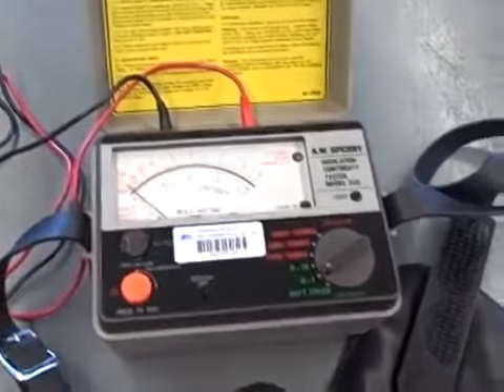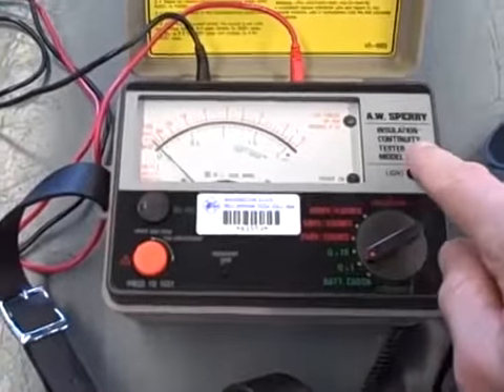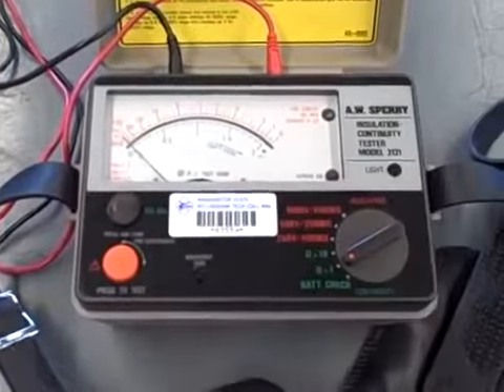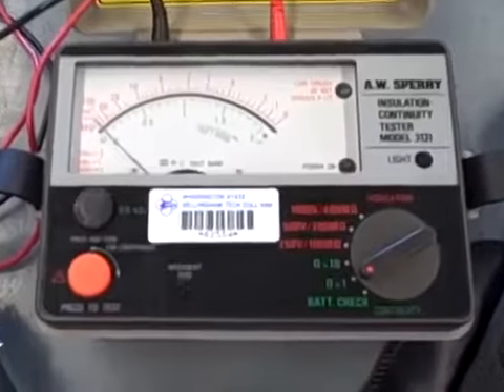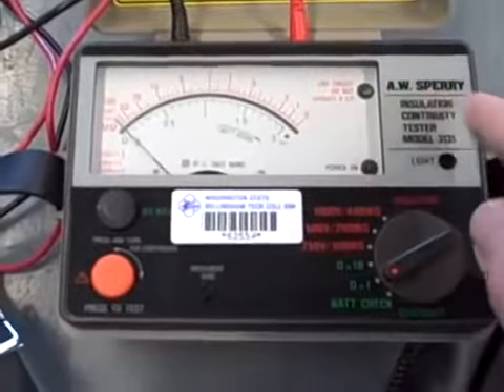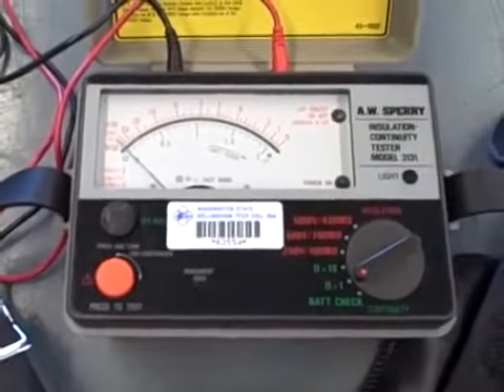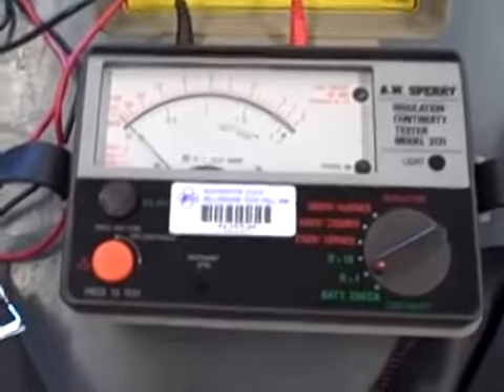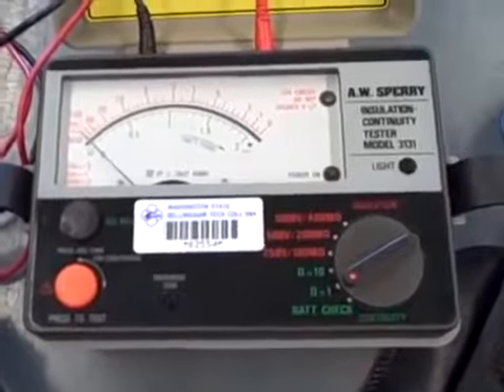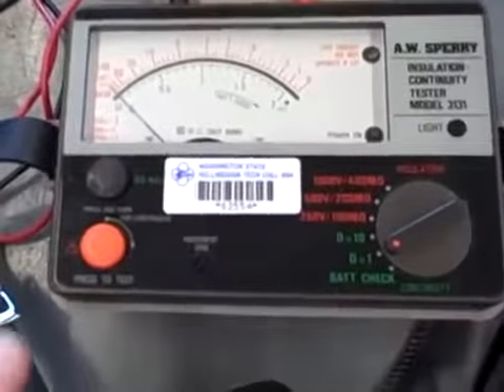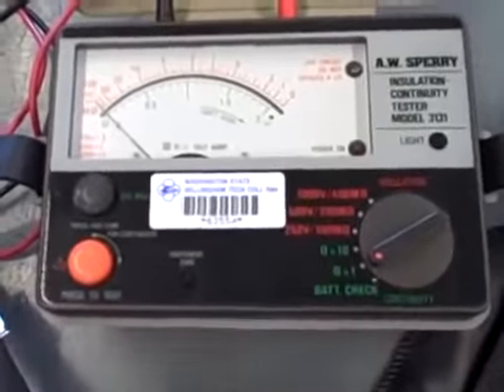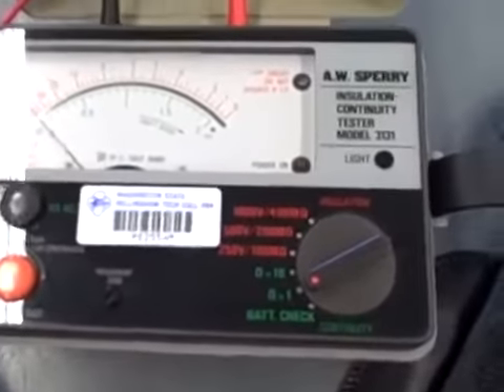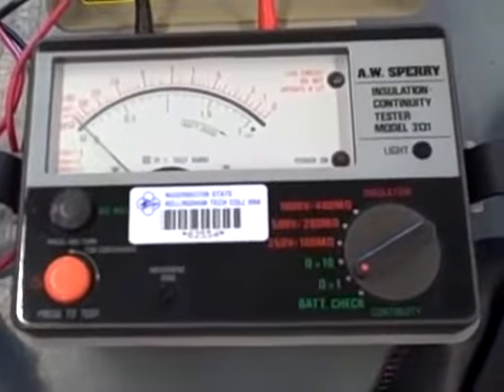What we're looking at here is a piece of test equipment referred to as an insulation continuity tester, otherwise known as a megger. This particular instrument is manufactured by A.W. Sperry. The word megger is actually a trade name with a different company. So you may hear electricians in the field refer to instruments as meggers even though they don't bear that name anywhere on the label. What this does is it functions as a specialized ohmmeter.